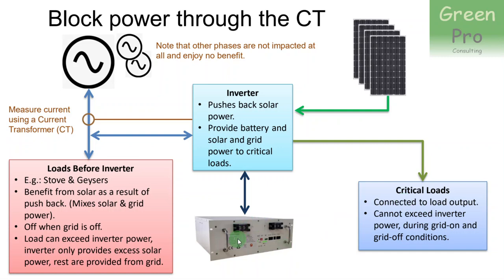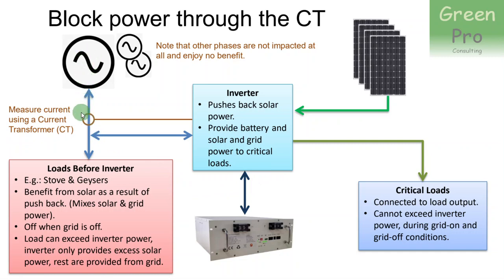These critical loads — if you get a power failure or load shedding in South Africa — will be fed by the battery. But the battery will not feed power to the loads that are before the inverter. However, if you have solar power, the inverter is capable of pushing power back to those loads. And where it's connected to the main switch coming into the property, into the main DB of the property, there you install a CT.